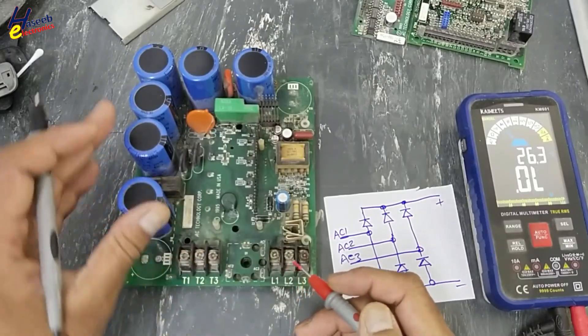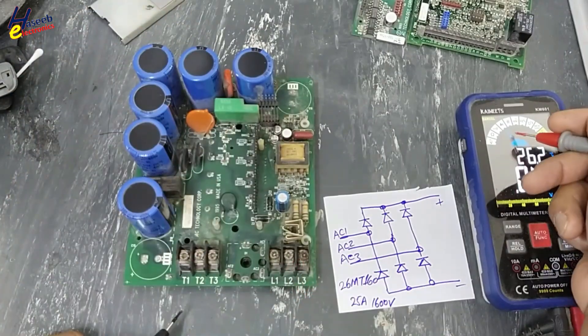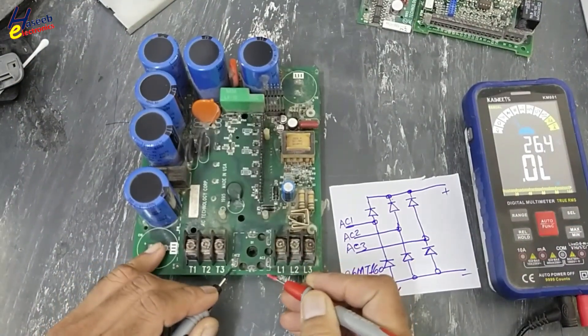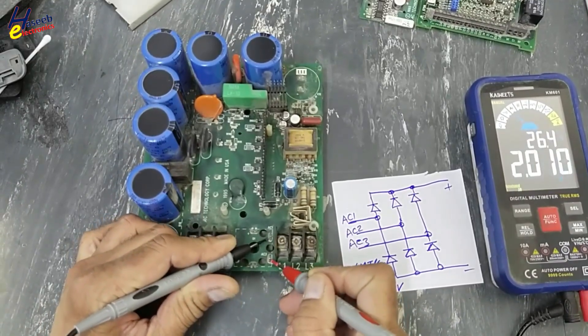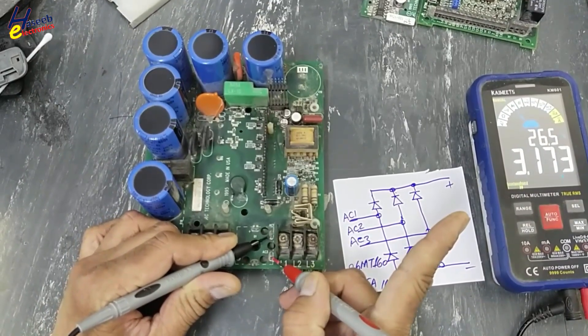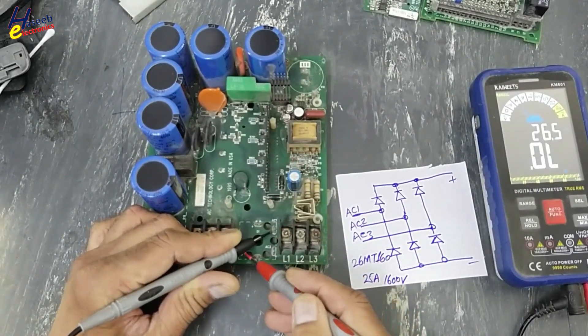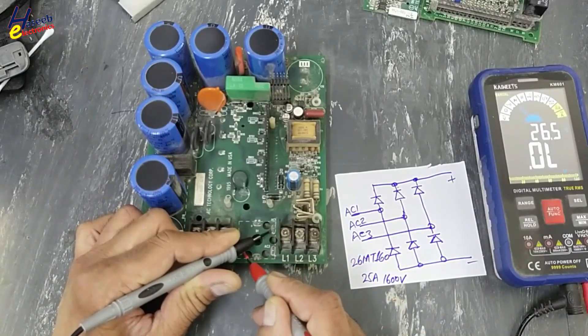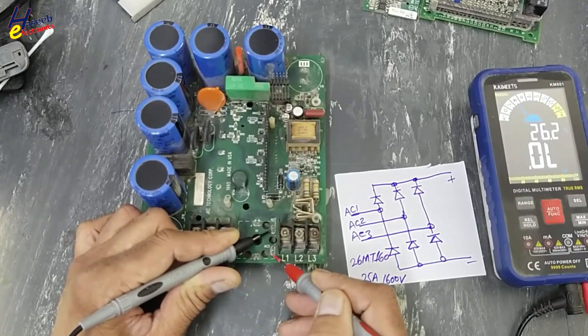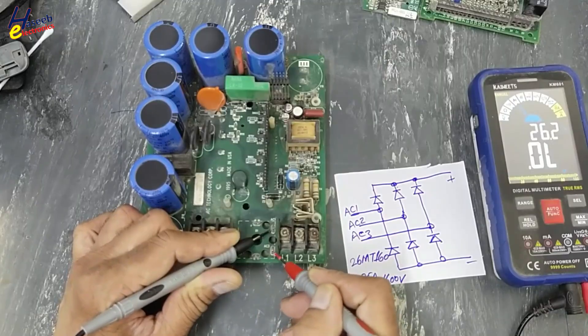Set multimeter to diode mode. Connect to AC1 terminal and AC3. Meter is showing some reading and then it is open circuit. AC1 and AC2, open circuit. Return back to AC3, now open circuit.